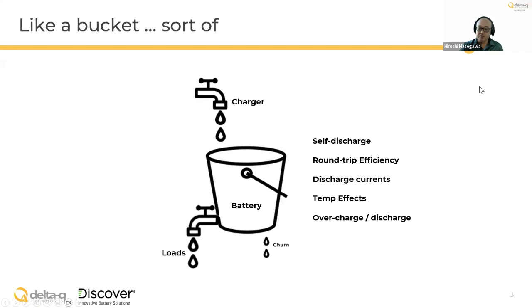This is due to factors such as internal resistance, temperature, and the nature of the chemistry of each battery, along with discharge currents. There's a phenomenon with lead acid batteries called the Peukert effect, meaning the higher you drain with your discharge current, the less overall capacity you get. Lithium has no Peukert effect, but discharges are strictly controlled by your BMS.